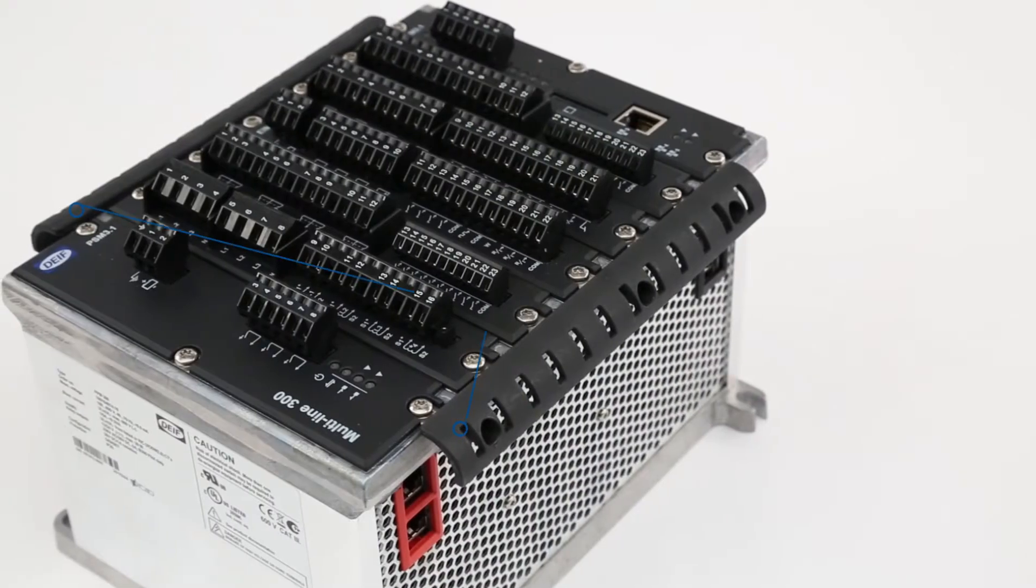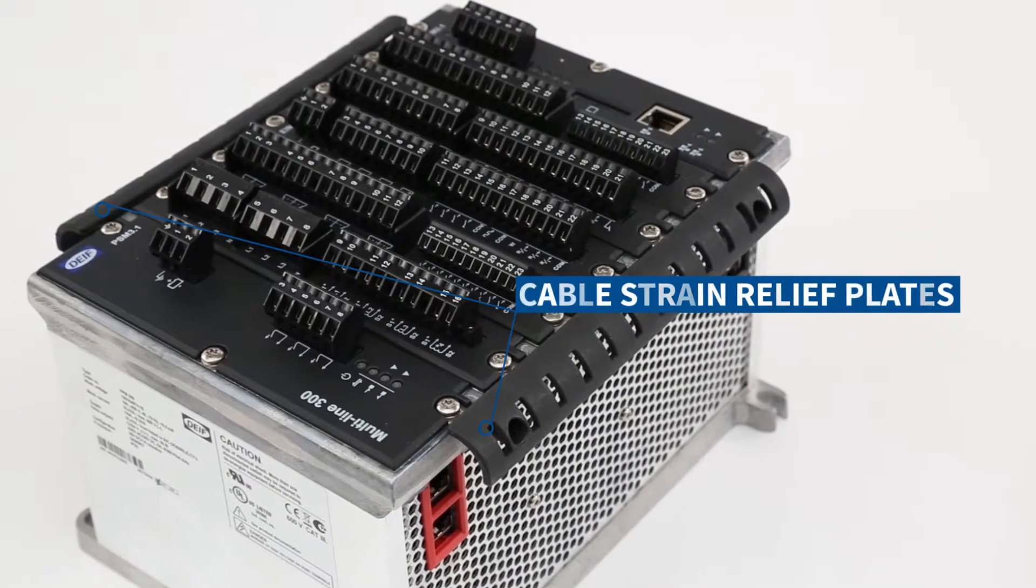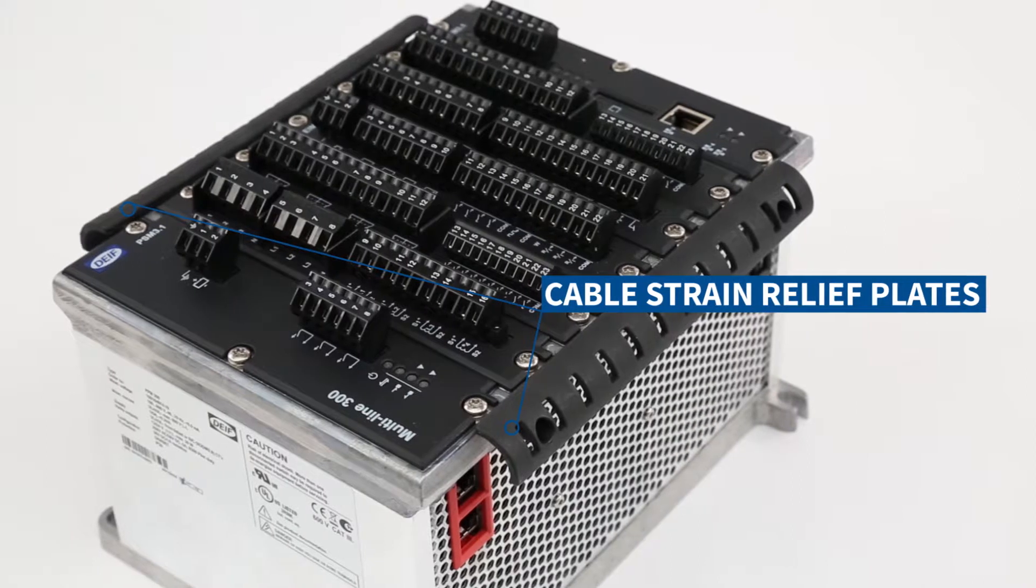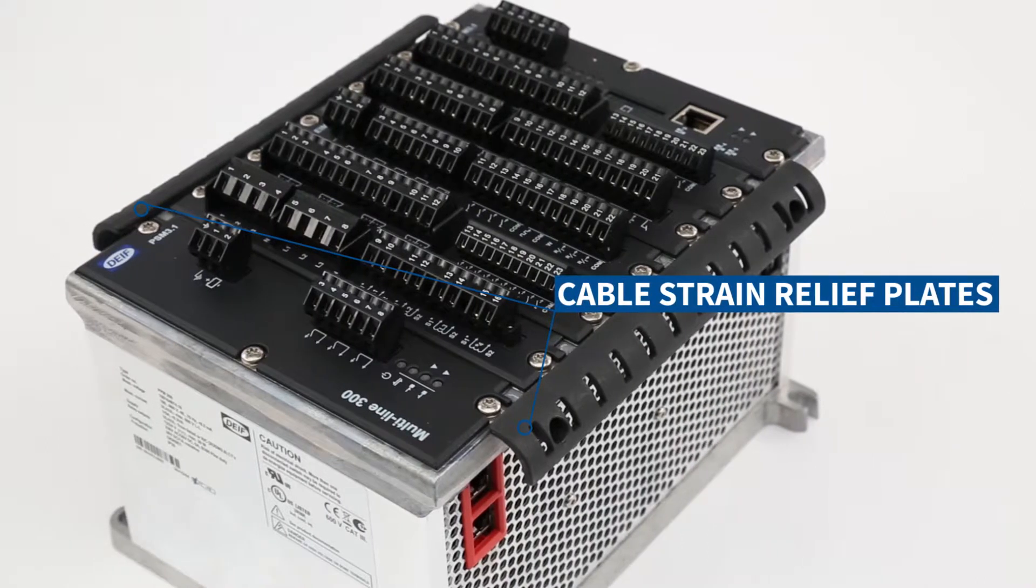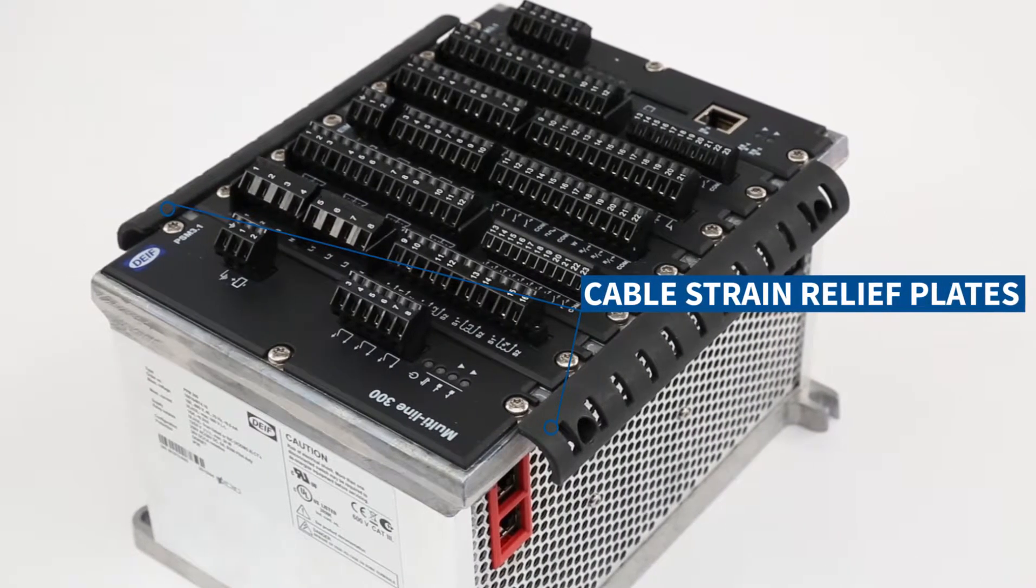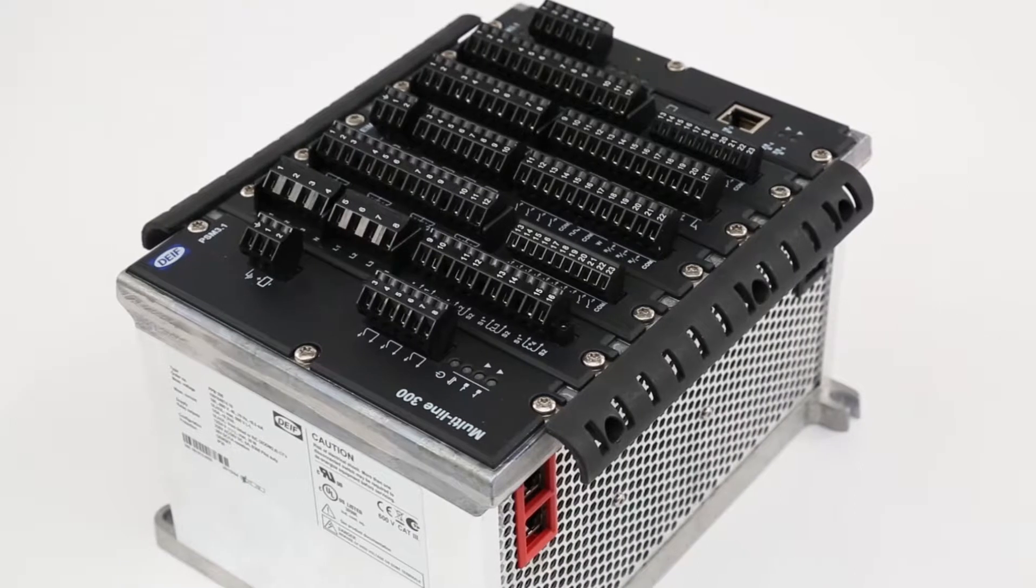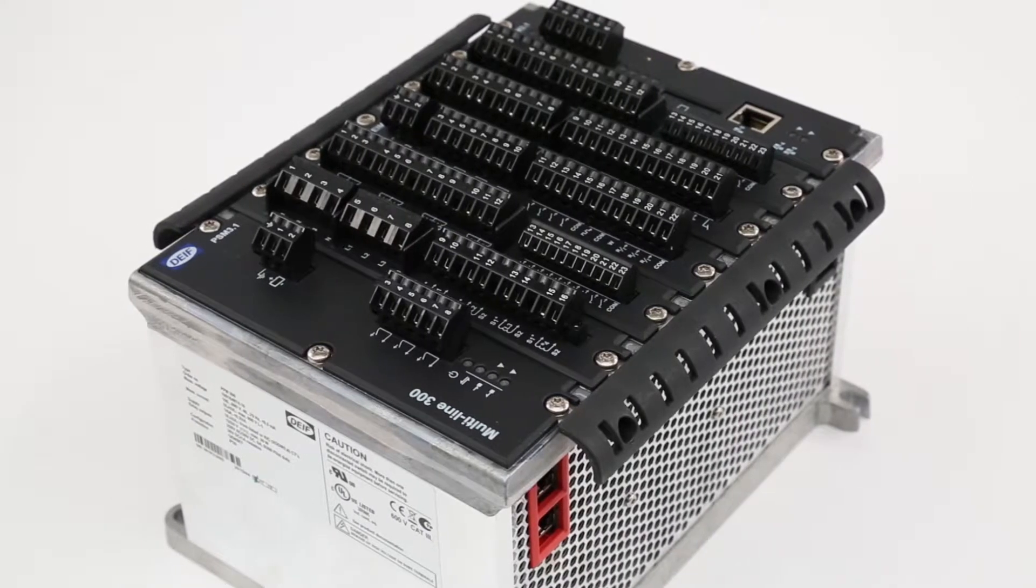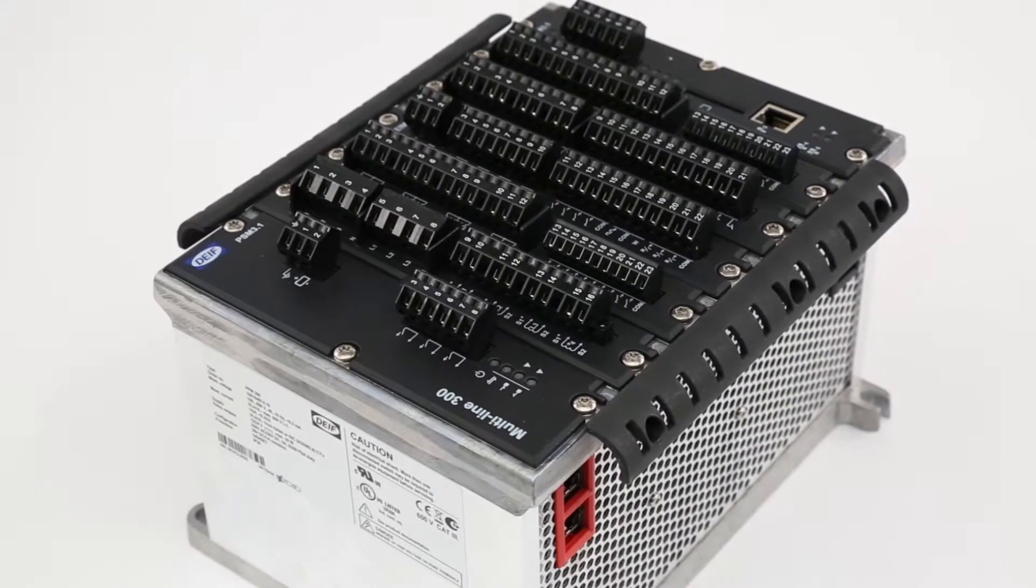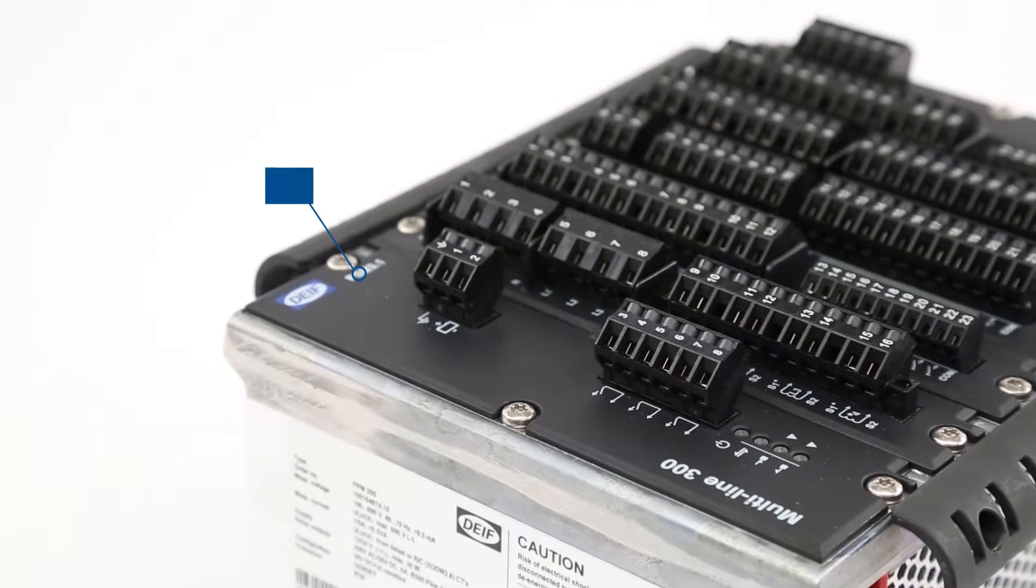The controller has cable strain relief plates mounted at the top and bottom for cable organization. The cable ties and routing must not block more than 20% of the ventilation.